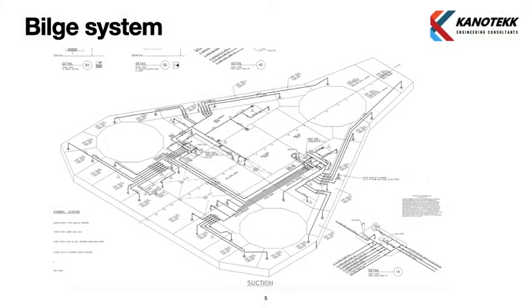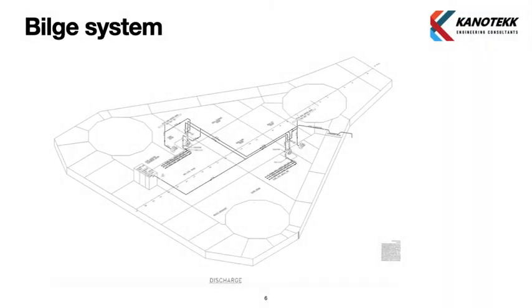Moving to the bilge system drawing, we can see suction of bilge lines from various parts of the rig. We can also see suction taken from preload tanks for the stripping function — when water accumulates inside the preload tanks, it needs to be pumped out in a process called stripping. The bilge system is employed for this stripping function in addition to its primary bilge suction purpose.